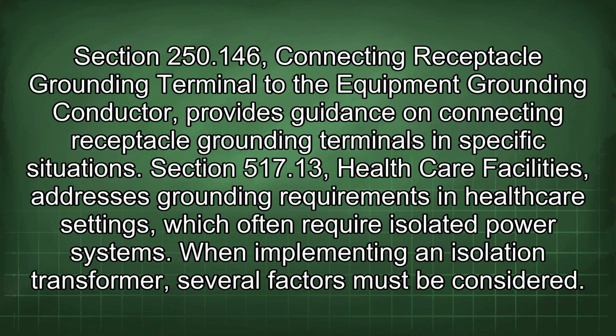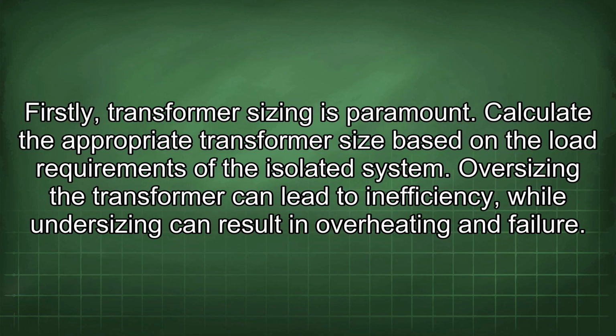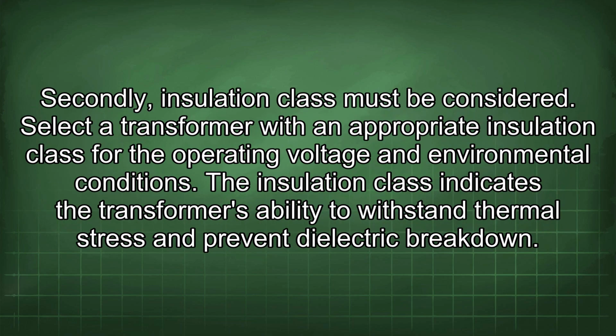When implementing an isolation transformer, several factors must be considered. Firstly, transformer sizing is paramount. Calculate the appropriate transformer size based on the load requirements of the isolated system. Oversizing the transformer can lead to inefficiency, while undersizing can result in overheating and failure. Secondly, insulation class must be considered. Select a transformer with an appropriate insulation class for the operating voltage and environmental conditions. The insulation class indicates the transformer's ability to withstand thermal stress and prevent dielectric breakdown.